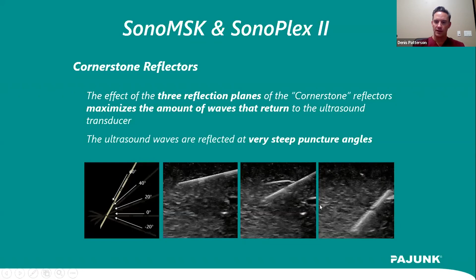But usually when you get steeper, here you're probably at a 45-degree angle, and on the right one you're probably at a 70 or 80-degree angle, those beams would come down, hit, and miss the ultrasound because they get reflected at that angle instead of going back up perpendicular to the probe. These cornerstone reflectors, set on the surface of the needle at different angles, allow the beam to be reflected back perpendicularly to the transducer to show up. So you can see that it doesn't matter what angle you're at, you can still see your needle.